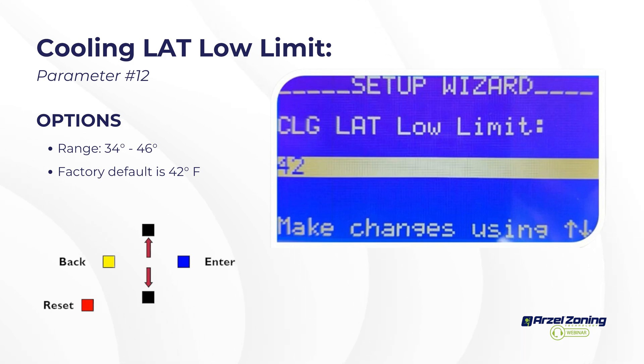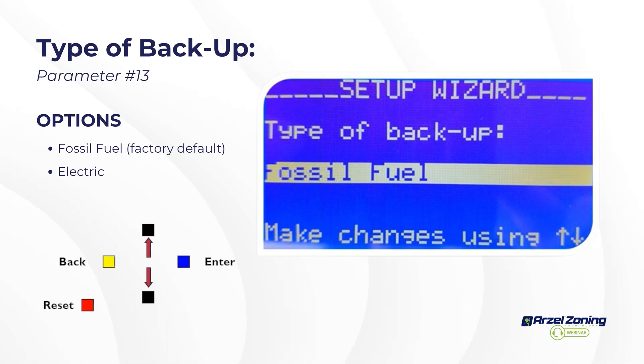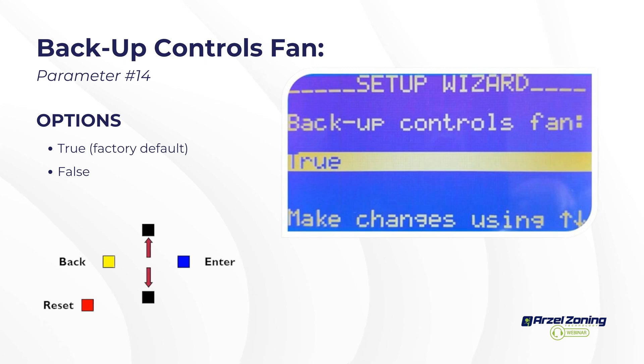The cooling low limit provides freeze protection for the coil — if plenum temperature dips below this value the compressor stages back, and if it stays below the compressor stages off. Type of backup heat: if set to fossil fuel, Y and W outputs cannot run simultaneously. If set to electric, W becomes an additional stage of Y — so first stage is Y1, second Y2, third W1, fourth W2.